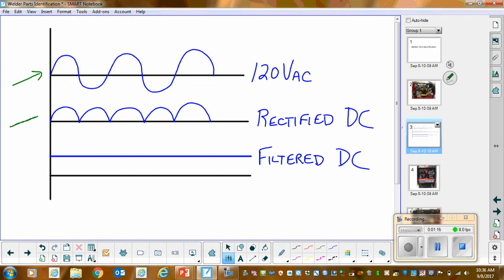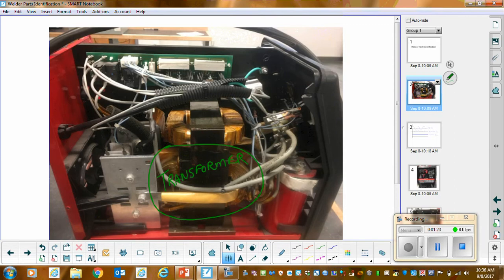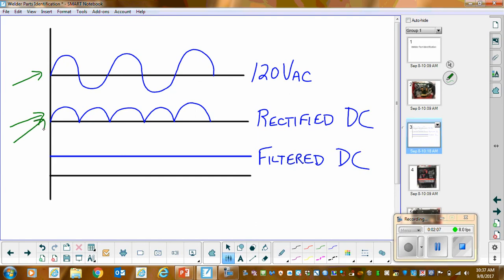Now what we're going to do is send it to what's called a rectifier, which is going to give us a waveform that looks like that. And so the device that does that, there's two devices on here. First of all, we have to rectify it. Now the rectifier is right here. Now you're probably looking at that thinking, well, it just looks like a plate of steel. In essence, it's a plate of aluminum, and it's actually a heat sink, and there's two of them. There's one there, and if you look real close, there's one there. On these heat sinks are diodes. They're called stud-mounted diodes. They're right here. You can see these are the anodes in this particular case. Again, you don't need to know what anodes are. But the idea of this rectifier is it takes the AC and it converts it to rectified DC. There's four diodes that help us with that. And like I said, when it does that, this is right here what you get for an output.